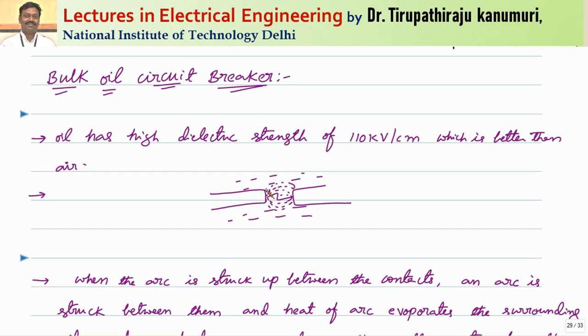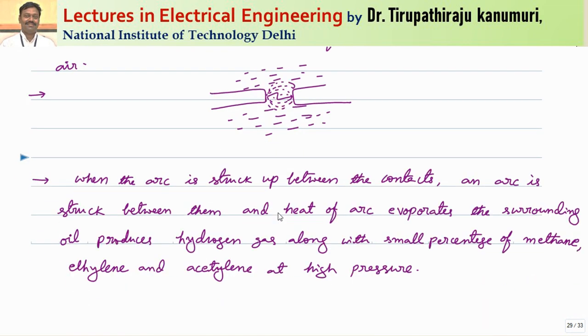The gas occupies so much volume that it creates turbulence in the surrounding oil. At natural current zero when the arc is extinguished, the bubble comes out — being lightweight it rises to the top of the tank. As it moves upward, the oil rushes in to fill that space and clears all the sediments of the arc. When the arc is produced, carbon is also produced, so the contacts may get carbonated; all those arcing byproducts are removed by the oil.